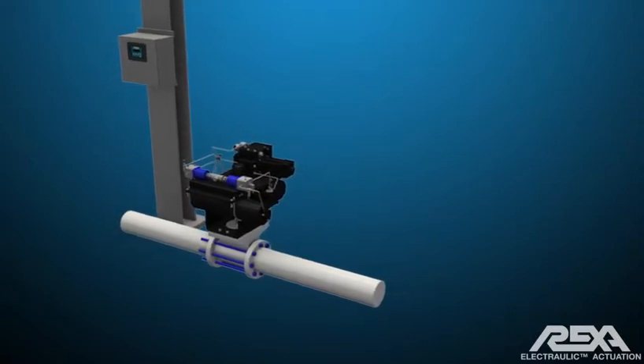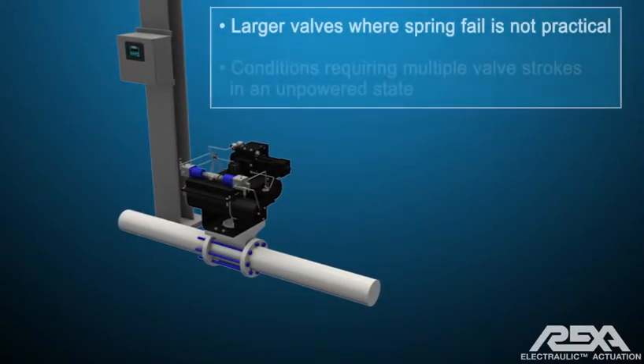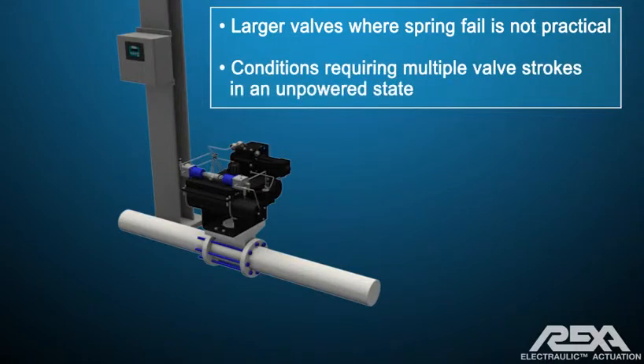Accumulator fail equipment is used for larger valves where the required torque or thrust is so great that a spring is not practical, and for conditions requiring multiple valve strokes in an unpowered state.